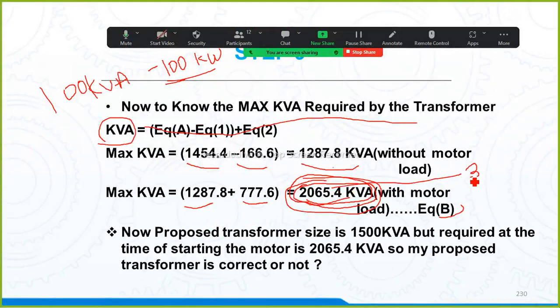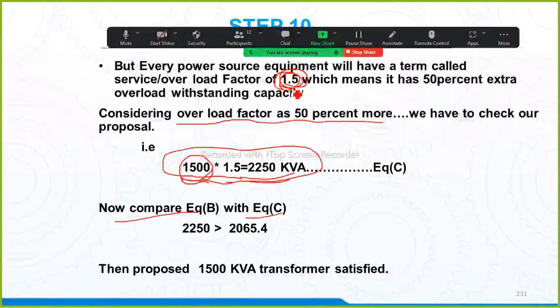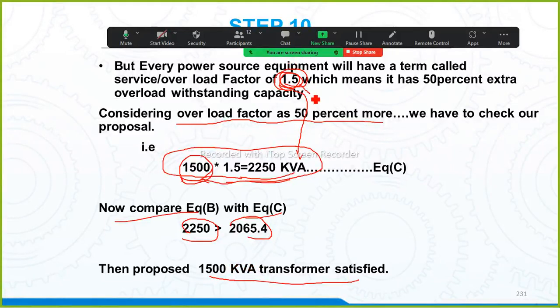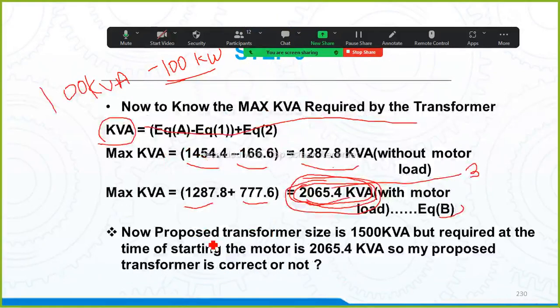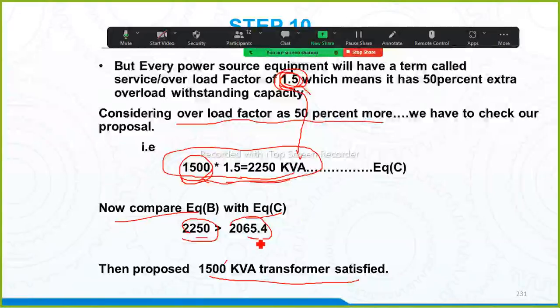फर्स्ट 3 minutes only. 3 minutes is very huge, and this transformer is also going to withstand 50% extra overload for 5 to 10 minutes. So 2250 is more than your 2065.4. इसका मतलब क्या है? 1500 kVA ट्रांसफॉर्मर इज satisfied because 1500 kVA का ट्रांसफॉर्मर है. 50% एक्स्ट्रा ओवरलोड लोगे तो कितना विस्टैंड कर रहा है? 1500 का केवीए रहे तो इट कैन विस्टैंड अप टू 2250. तो अगर आपका मोटर स्टार्टिंग के टाइम में अधिक गुना भी लोगा तो उसका 2065.4 के हिसाब से लेके चलोगे तो ये प्रपोज ट्रांसफॉर्मर सैटिस्फाइड.